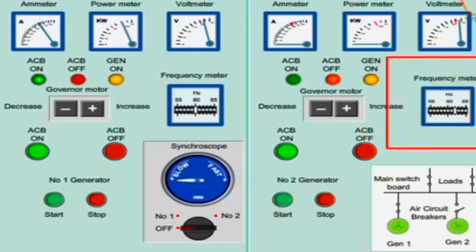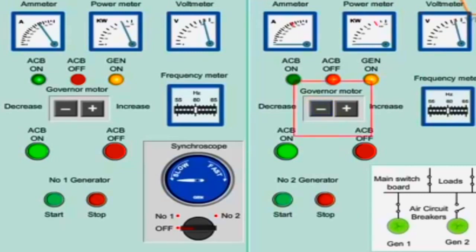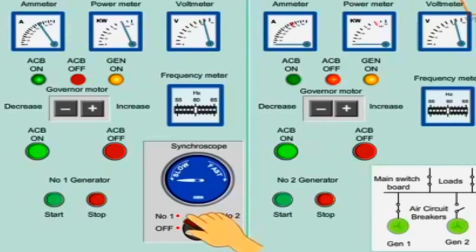Check the frequency of the generator. If the frequency is 62 Hertz, decrease the frequency of the number two generator. This is done by using the governor motor control switch in the panel, which decreases or increases the speed and hence the frequency of the generator. Switch on the synchroscope selector to number two generator.